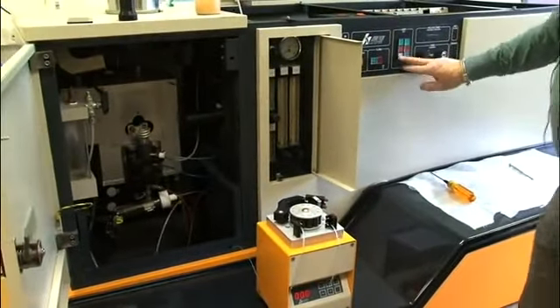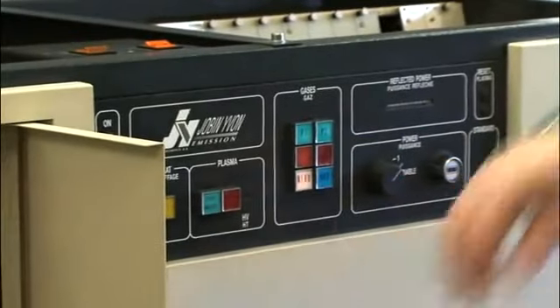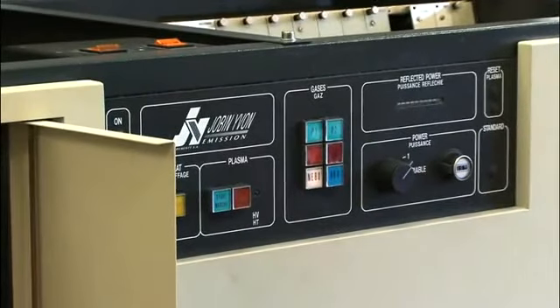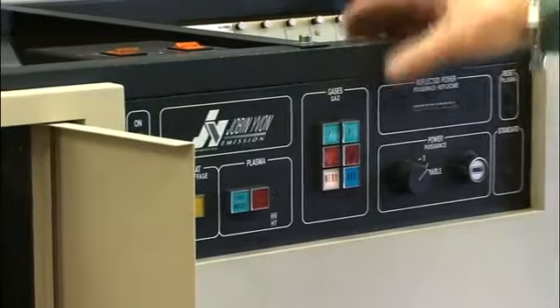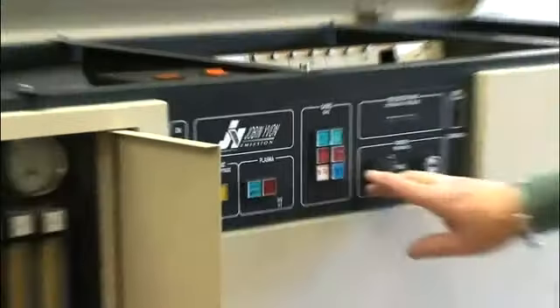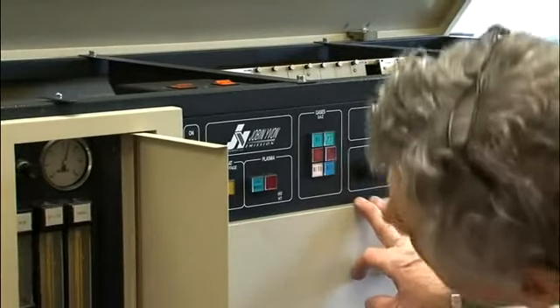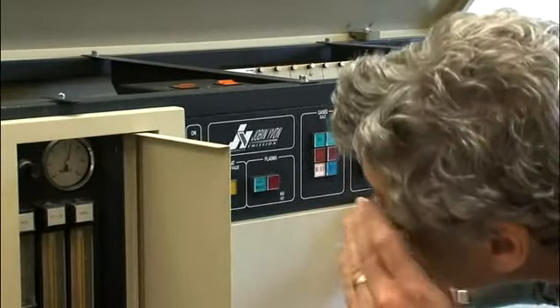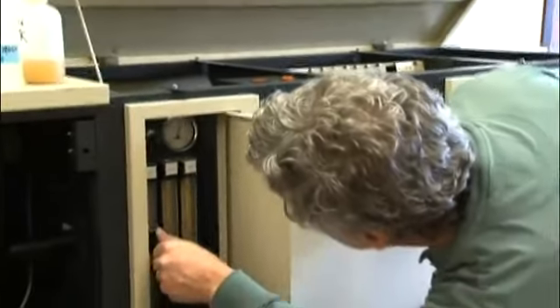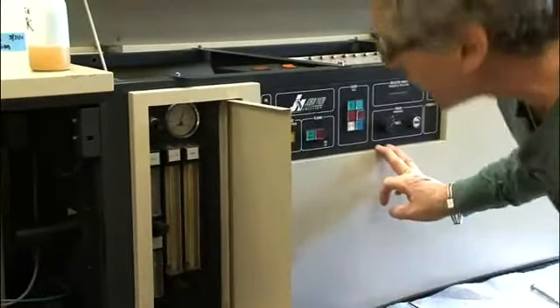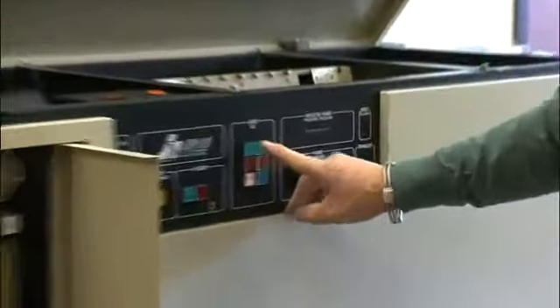So what you want to do then first, before you start, turn all the gas. We're only using these 3 gases here: your plasma gas, your sheath gas, your nebulizer gas. If you were to run an organic sample, you're going to use P2 also. What that does is it gives you 16 liters, and you also run your auxiliary. I don't know where that's set at. 0.6, that's about right. But we're not using those 2.